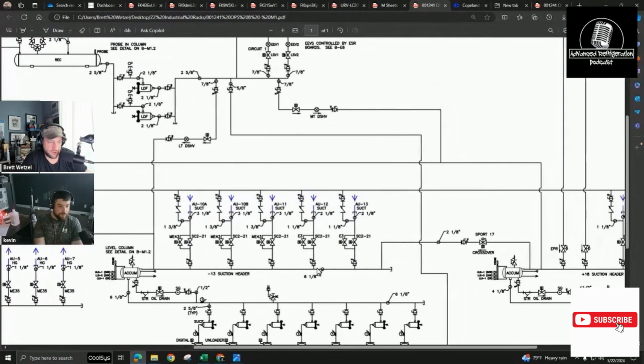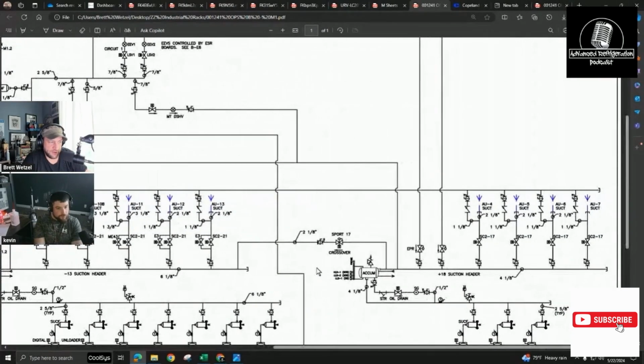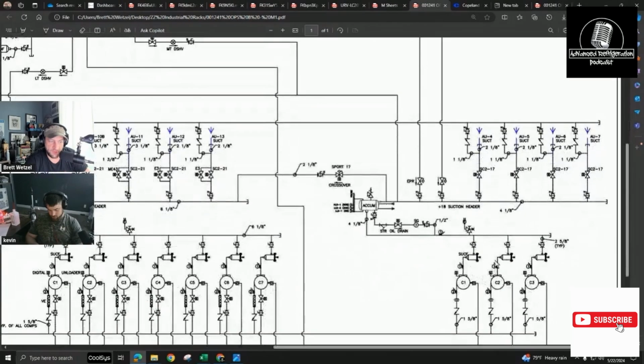Oh, look what else they got here. So here's your 18-degree section. And then they have a crossover valve. I've seen this on some boxes, on big facilities where they don't have a terribly big load, where the doors are shut, they might not be right on the dock or whatever, where it really doesn't need the capacity of the compressors that are down here, especially in the nighttime. But the freezers always do, because they usually always have something going into defrost and coming back into refrigeration.